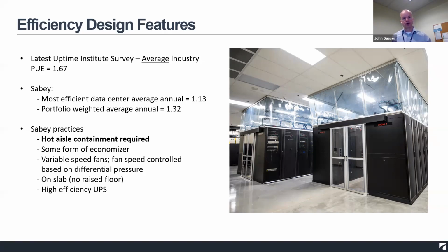You can compare it where mechanical cooling is running that air conditioner, and economizer is similar to opening the window and using a fan. Speaking of fans, we use variable speed fans at all of our data centers, and we control the fan speed on differential pressure. So what we're trying to do there is match up the air that we're moving with our air handlers to the air that the servers are using. With containment, you can do that via differential pressure. As the server fans pull more air, the differential pressure set point goes out of whack, and the controls act to increase the fan speed and catch up with that airflow. And it happens very seamlessly if you have good containment. We build our data centers on slab, so we have not built a data center with raised floors since 2008. That was very much an unusual thing back in 2008, but now it's becoming more common.